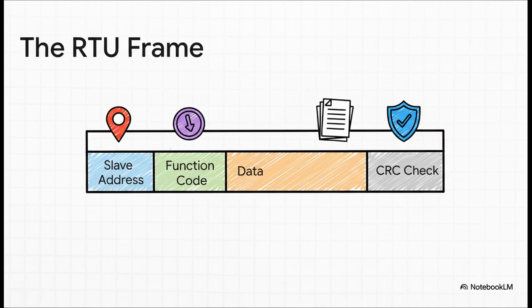So let's take a quick look at that popular RTU message frame. It always starts with the slave address, basically, who is this message for? Then comes the function code, what do you want them to do? Then you've got the data itself, and it all wraps up with this crucial 2-byte CRC check. That's a powerful little bit of math that makes absolutely sure the message arrived perfectly intact with no errors.